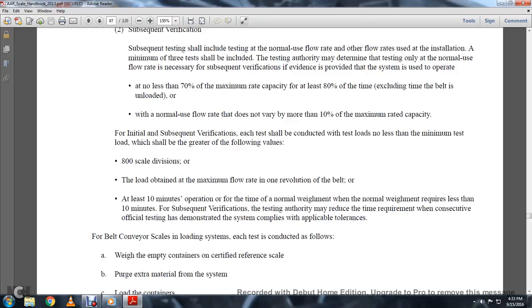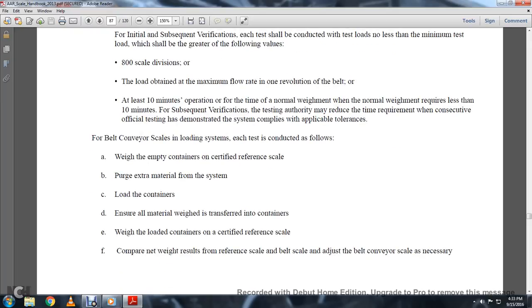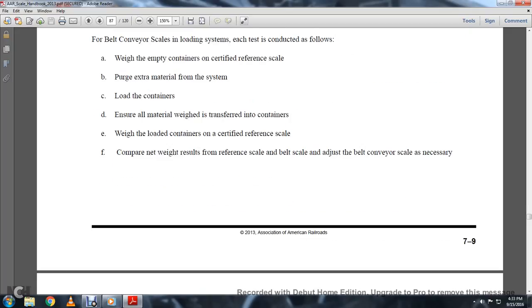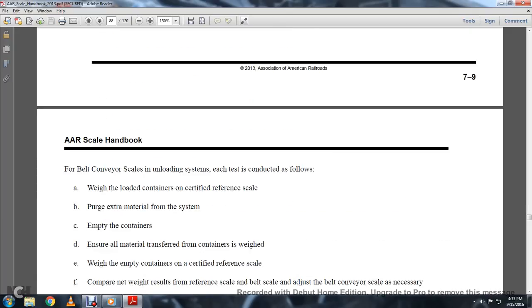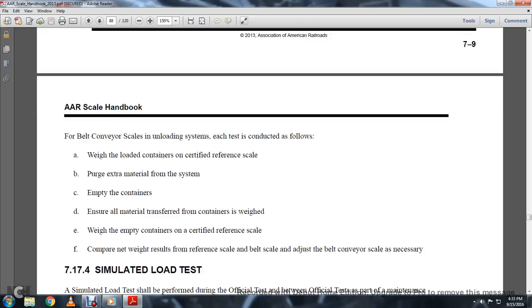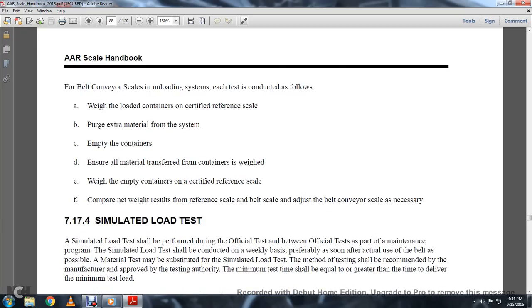For belt conveyor scales, the loading system at each test is conducted as follows: weigh the empty containers on a certified reference scale, purge extra material from the system, load containers, ensure all material is weighed and transferred into the containers, weigh the loaded containers on the certified reference scale, compare the net weight from the reference scale and belt scale, and adjust the belt conveyor scale as necessary. For the unloading system, weigh the loaded containers on the certified reference scale, purge extra materials, empty the containers, ensure all materials are transferred, weigh the empty containers on the certified reference scale, and compare the net weight results, adjusting the belt conveyor if necessary.